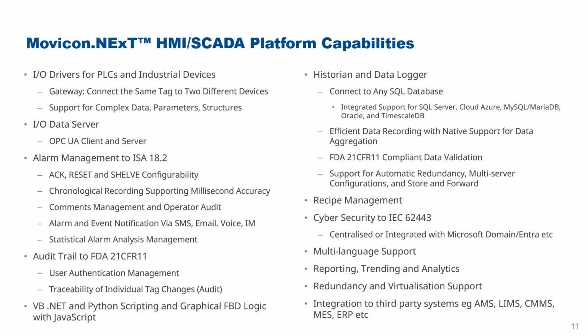One of the issues with HMI SCADAs is if you're logging lots of data, you can very quickly fill up the database. So data aggregation, what that does is on a timed basis, it eliminates older values and it aggregates those into a smaller set of values, such as minimum, maximum and averaging over a specific period. And then you can delete all of the raw values and just use that aggregated data.